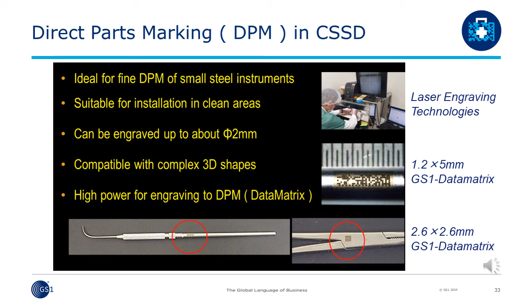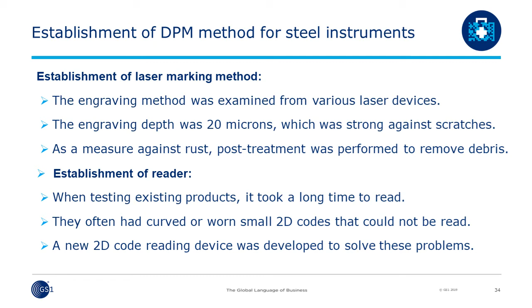Establishment of reader. When testing existing products, it took a long time to read. They often had curved or worn small 2D codes that could not be read. A new 2D code reading device was developed to solve these problems. Next, we will introduce the direct parts marking reader that we have developed with our know-how. This reader is specifically designed for DPM technology and surgical instruments.